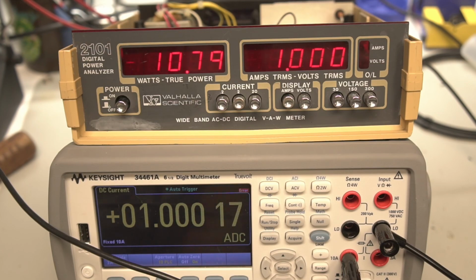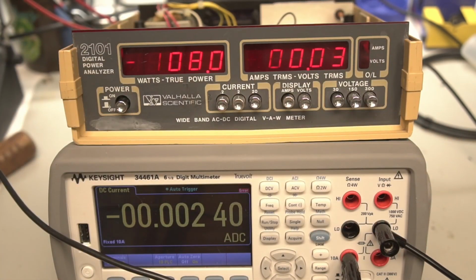I'm not going to be able to do the 20 amp range, at least not all the way. We can bring it up probably about, we're also limited to 5 amps on my power source because I'm using the 30 volt O1 right now. So we'll go ahead and put it in the 20 amp range and then take it up to 5 amps and see what we get. So that seems close enough. So I think I'm just going to leave the current calibration the way it is. I'm not going to touch that one.